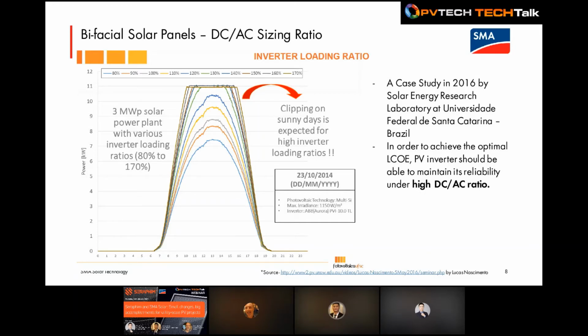A case study back in 2016 by the Solar Energy Research Laboratory in Brazil conducted research on the DC-AC sizing ratio. As you can see here, if you use 100%, which is a 1:1 sizing ratio like I said, for the 10 kilowatt range you only get less than 9 kilowatt, and you will need to oversize on the DC side, let's say 1.1 or 1.2. So you need to go to between 1.1 and 1.2 to be able to reach the actual 10 kilowatt output, as you can imagine.